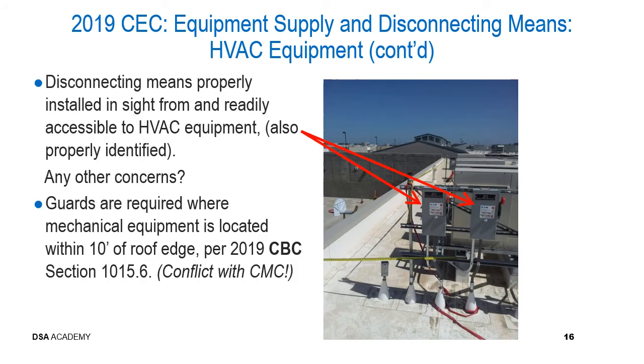This picture on the right-hand side of this slide shows an image taken on one of DSA's projects, where you can clearly see the disconnecting means located within sight and readily accessible of the air conditioning units that you can see in the background in this slide. You may also be able to see, I know it's a little bit difficult, the black labels on the top of each of those disconnects identify, as is required, the actual equipment numbers or the equipment ID that each of those disconnects serve. Now the question is, looking at this slide, can you see any other concerns? And we've basically given the answer just in the second bullet.